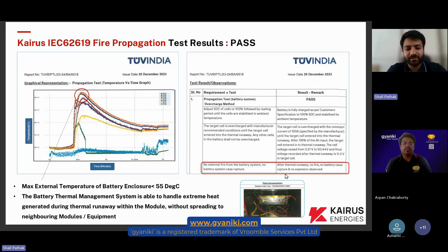What happened during the test is, at 50 volts, the cell erupted and went into a venting action. But due to cutoff of oxygen, no cell on the neighboring side had any impact. So the cell that was meant to go into thermal runaway bulged and went into a venting action, but there was no explosion, and the entire battery system remained as it is. That is how we passed the fire propagation test.